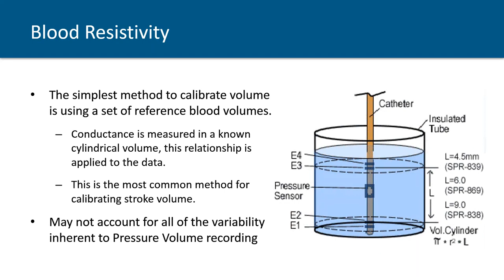You do a linear regression, and then this is automatically applied within your software package, so that all conductance values or relative volume units, depending on which software you're using, are now automatically converted to known volumes based on this calibration. It's important to keep in mind that when you're using this calibration technique, the implicit assumption is that the gain that you're applying here, the calibration factor, is relatively the same from animal to animal. The only slight variability would be how you place the catheter within the cuvettes. Otherwise, you're just assuming that the calibration you apply from these cuvettes, since they're identical blocks that you're using in each experiment, is the same calibration applied to all studies that you will be doing.